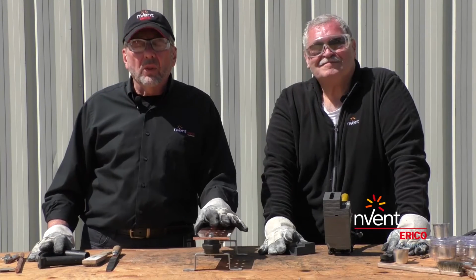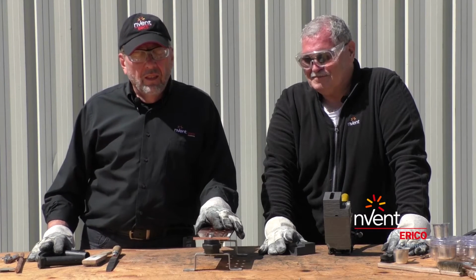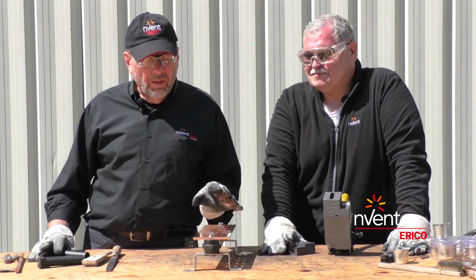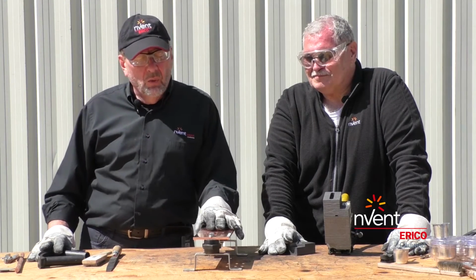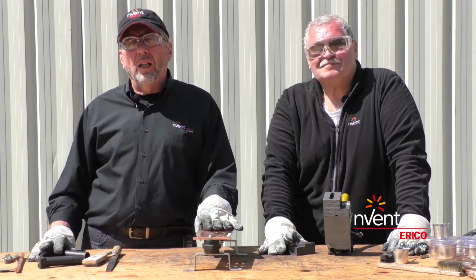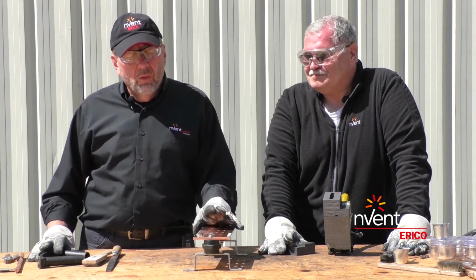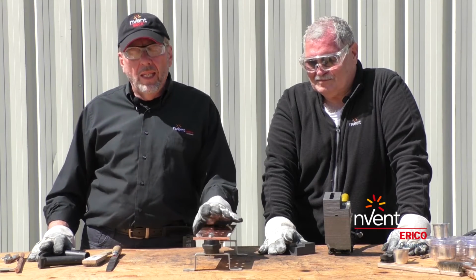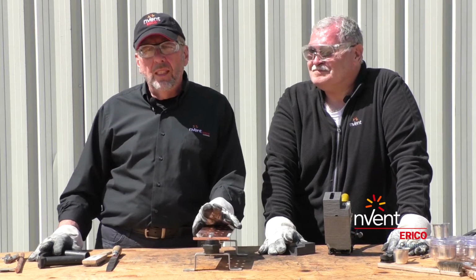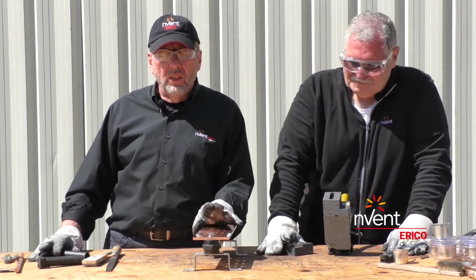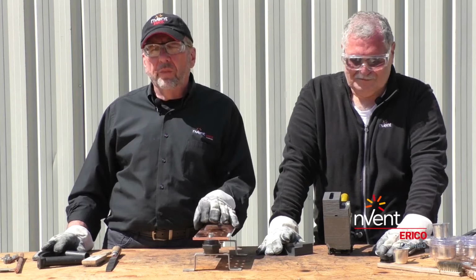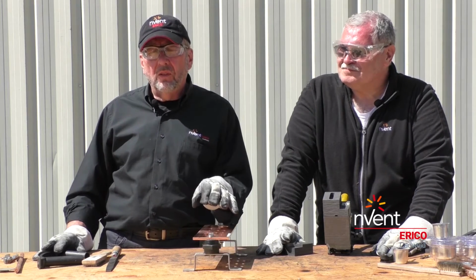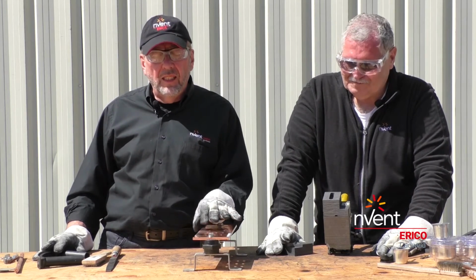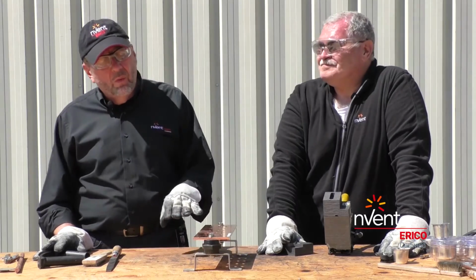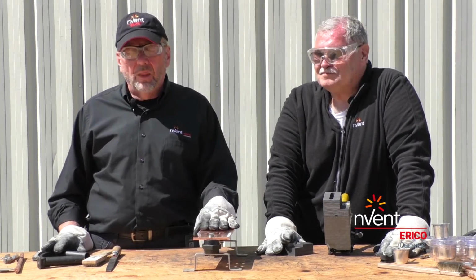So the next connection we're going to make is a connection to a copper object. Ground bar, earth bar, copper strip - whenever we make connections to anything copper, we need to do our connection in such a way that we overcome the copper's natural tendency to act like a heat sink. So we can't weld to the flat face of the copper object.